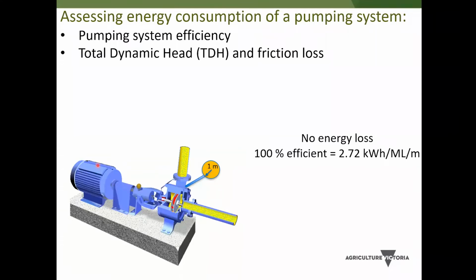So for the pumping system efficiency, if it's 100% efficient, so there's absolutely no energy loss in that pumping system, it's all converted into the movement of water, we'll use about 2.7 kilowatt hours per million litres of water pumped per metre of pressure we're pumping against. But the systems are never 100% efficient.